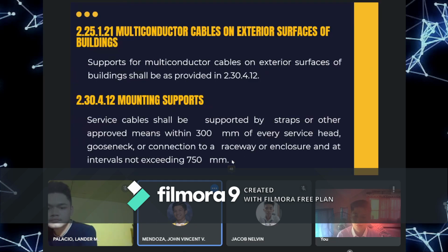Next slide please. So, lipat naman tayo sa 2.25.1.21, yung multi-conductor cables on exterior surfaces of the buildings. Supports for multi-conductor cables on exterior surfaces of buildings shall be provided as in 2.30.4.12. So, sabi dito is yung sa 2.30.4.12, yung mounting supports natin, dapat yung service cable shall be supported by straps or other approved means within 300 millimeter of every service head, goosenecks, or connection to a raceway or enclosure, and at intervals not exceeding 750 mm.